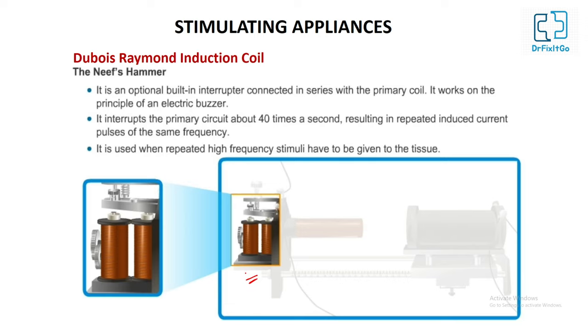The Neef's Hammer is a built-in automatic interrupter connected in series with the primary coil of the induction coil. It works on the principle of an electric buzzer or electrical bell. It interrupts the primary circuit about 40 times per second, resulting in repeated induced current pulses of the same frequency in the secondary circuit. It is used when repeated high-frequency stimuli have to be given to the tissue.